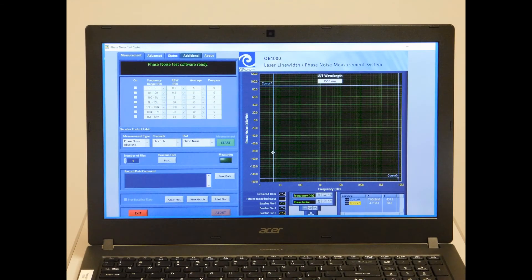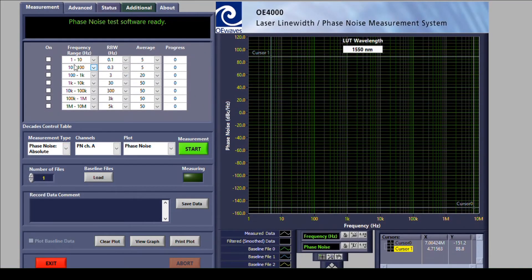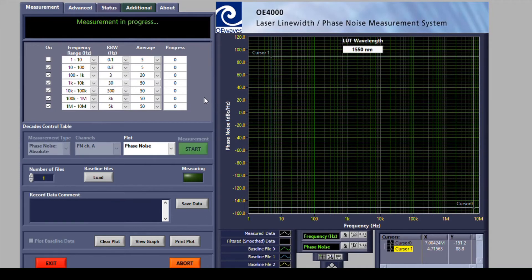We will start with a demonstration of a phase noise measurement. First, the user selects the desired Fourier or offset frequency range, shown here by the top left decade table — in this case, starting from 10 Hz to 10 MHz. The user can select the resolution bandwidth and number of averages for each decade or keep the default values. Then, when ready, simply press the green start button. The system will then start a completely automated measurement via internal optimization and measuring the sensitivity.